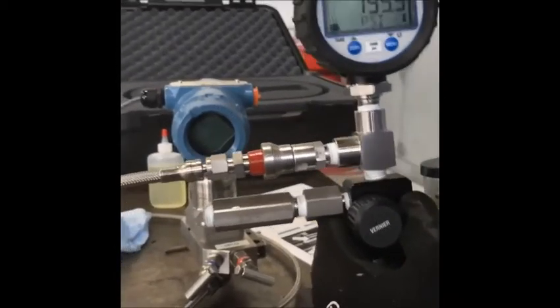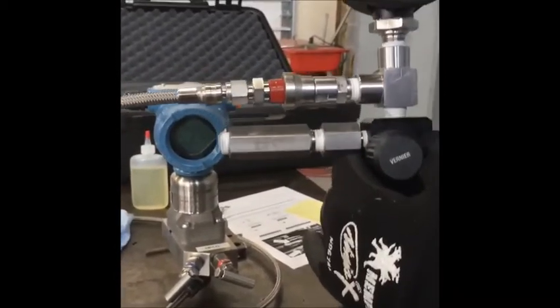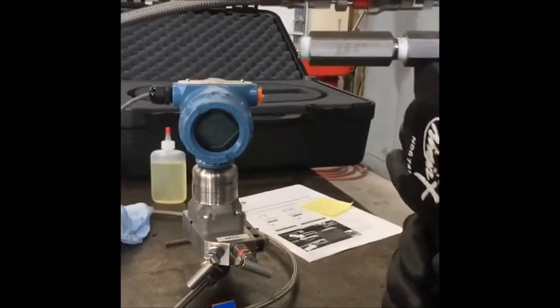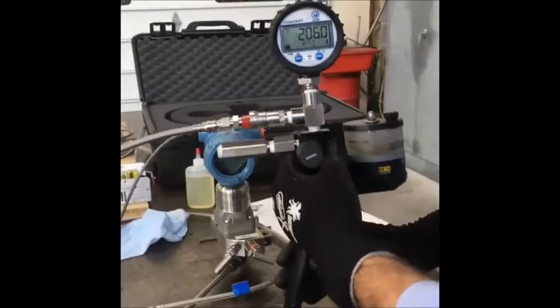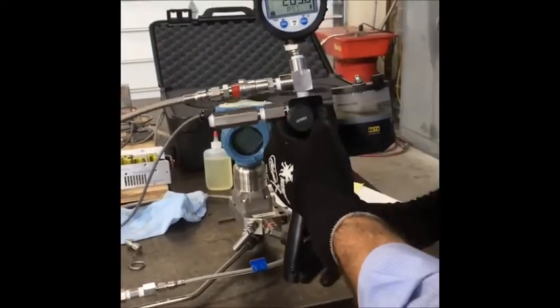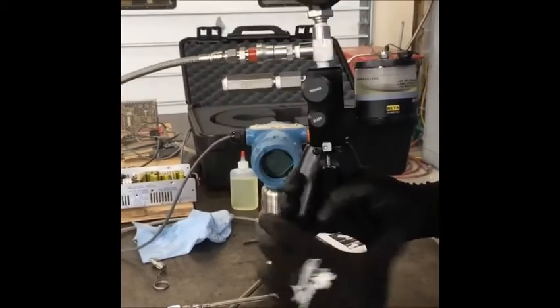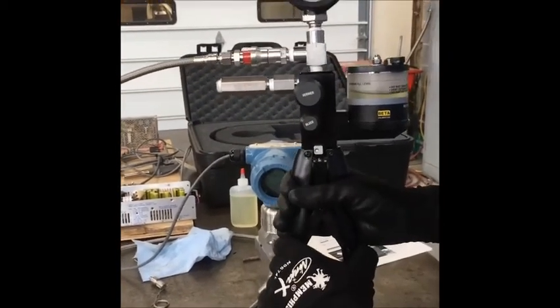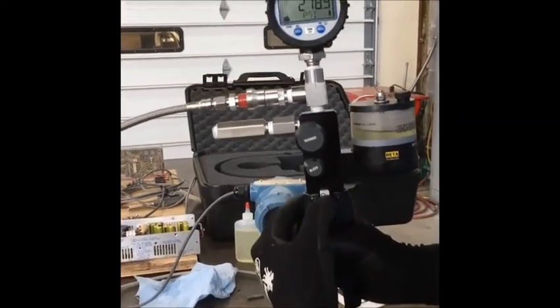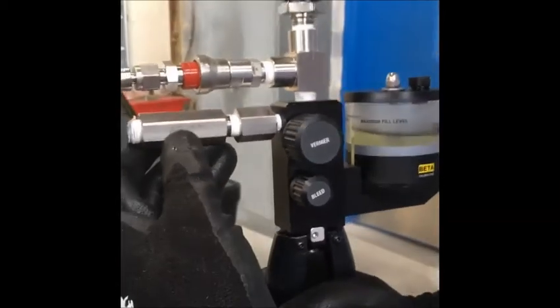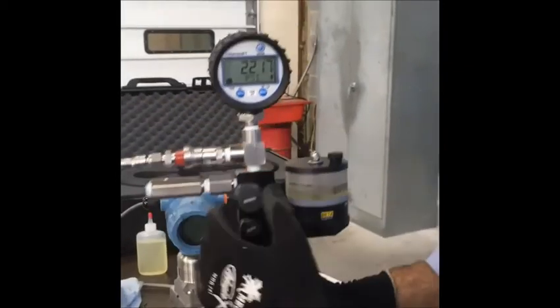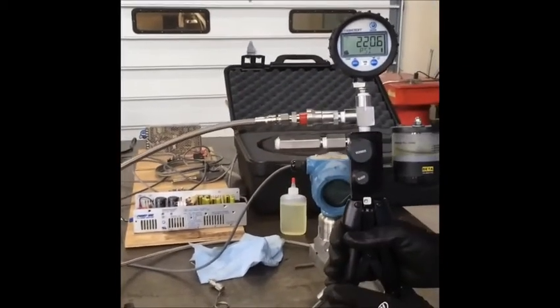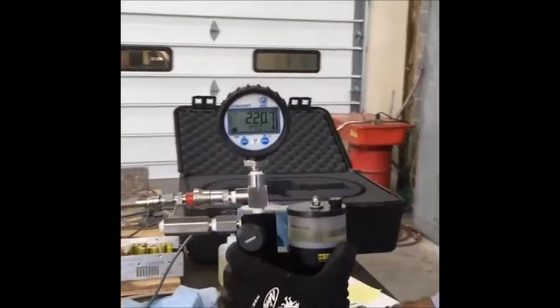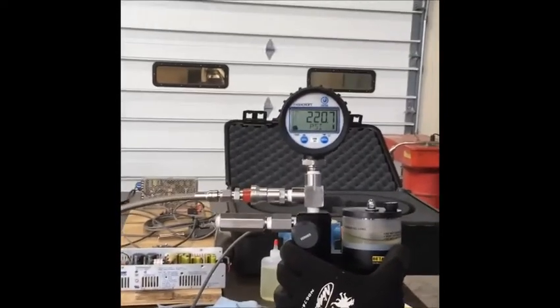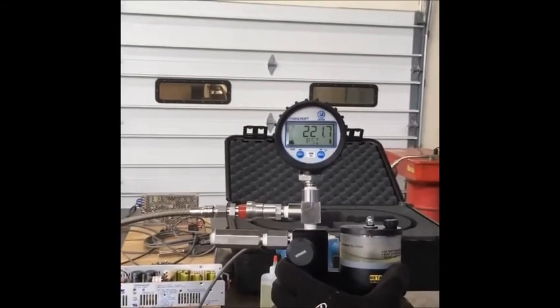Now we're going to simulate a high pressure cutout at 225. Let's see, I guess we'll do it in 225 PSIG, which will actually be about 230 over here. So as you see, as I get close, now one thing we need to do with this pump is as we're approaching our pressure, we're going to push in this button that will take us out of the priming mode into pump mode, and then the stroke on the pump is a lot less. But that allows you to slow things down so you can gradually approach the pressure. Now you can see it, I'm already at 220. I said I'm going to set it for 225. So if I just go a little bit more, okay, there I'm at 221.